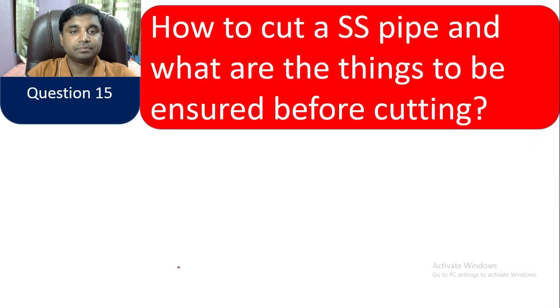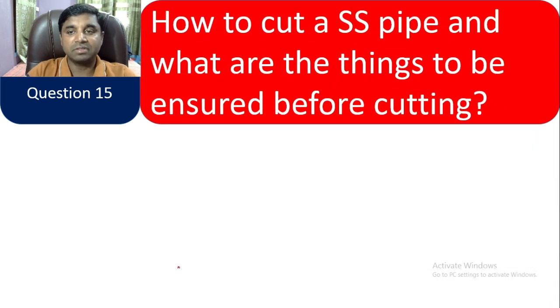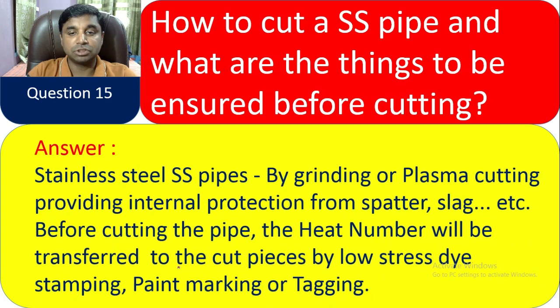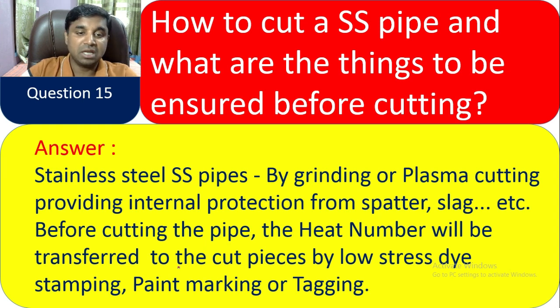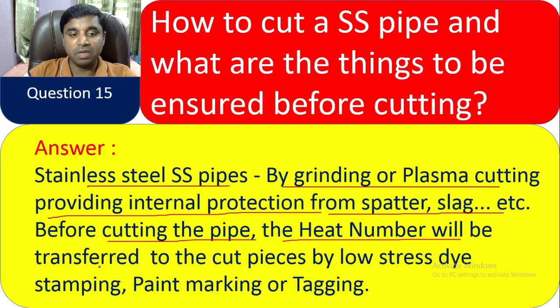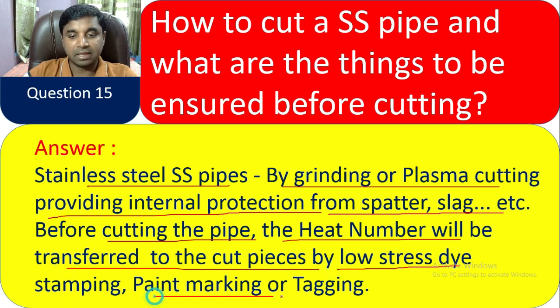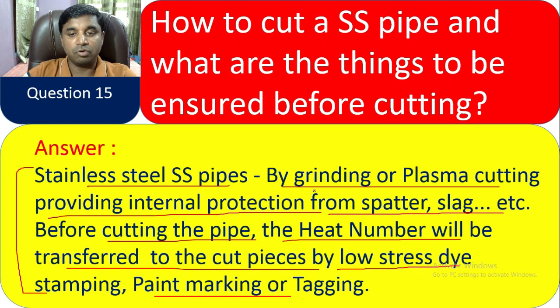Question 15: How do you cut a stainless steel (SS) pipe, and what things must be ensured before cutting? Cutting is done by grinding or plasma cutting, providing internal protection from spatter and slag before cutting. The heat number will be transferred to the cut pipe by low-stress die stamping, paint marking, or tagging. These requirements apply not only to SS pipe but also to carbon steel pipe.